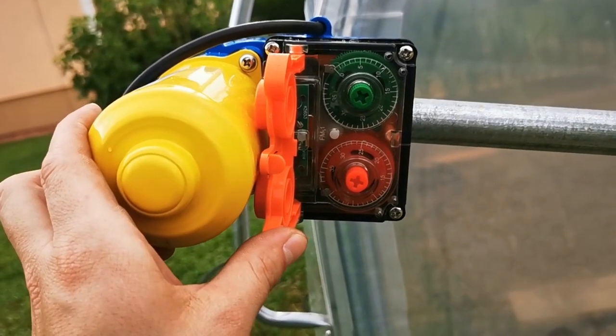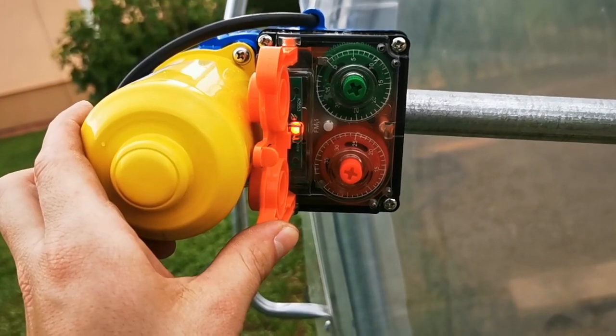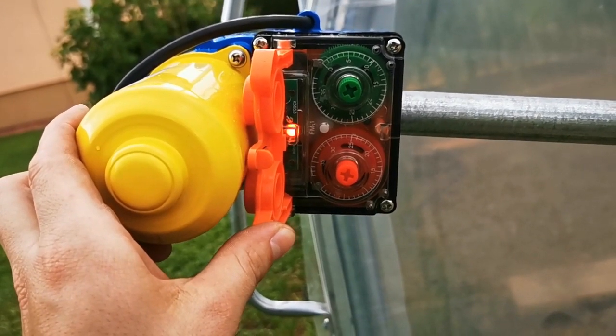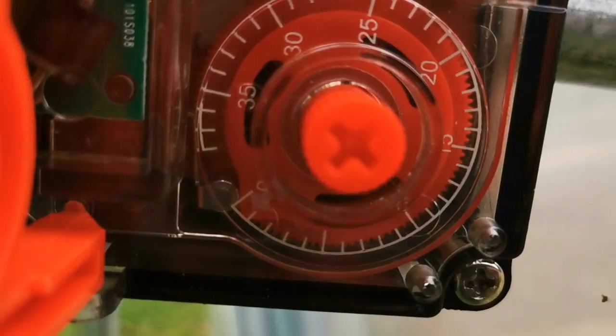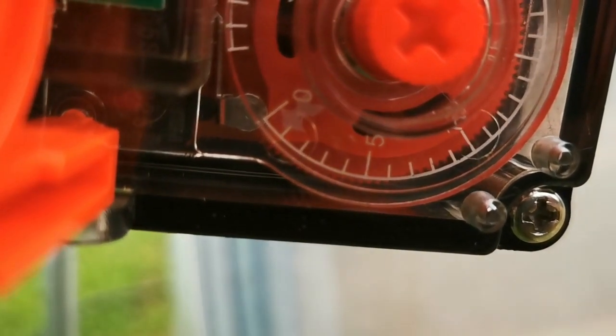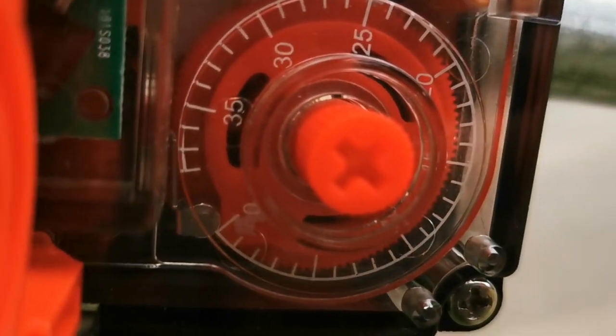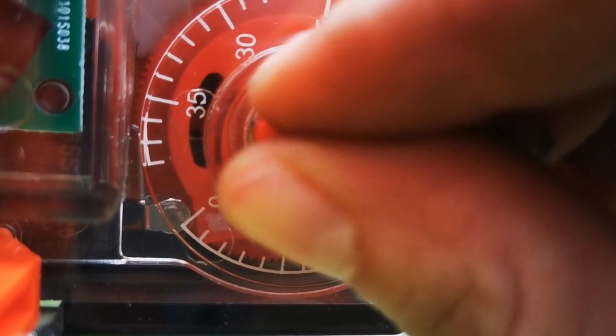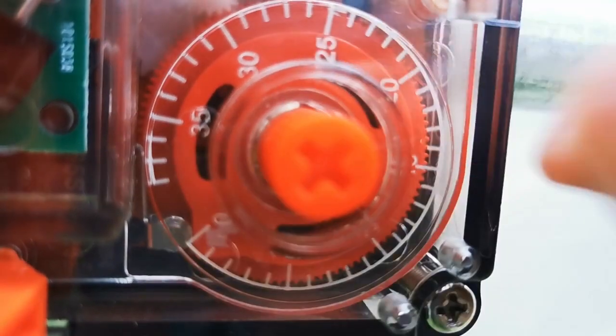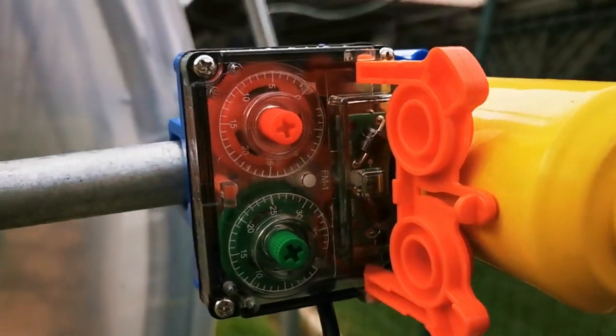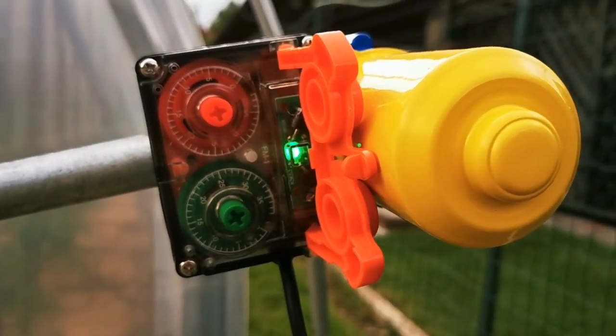First, we set the lowest limit switch. Hold the down button on the box for 1 second to turn on the engine light. The color of the light tells us which of the 2 limit switches we are setting. In this case, it is red. Set the arrow on the red switch as close as possible to the limit switch contact. We do the same on the other side.